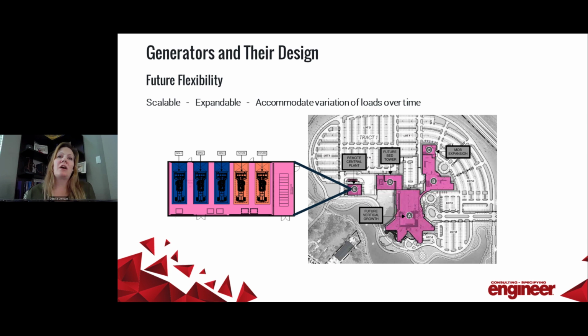All right, so let's now talk about how we make our generator system future-proof by providing the most flexible and scalable design as possible that fits within our owner's budget. So it requires appropriate space planning, adequate capacity in the distribution systems. So while you're assessing the loads and determining that ultimate redundancy desired, it's really important to understand the ultimate planned growth for a facility. You know, perhaps there's planned expansion on the campus, or maybe they can't afford to put all of their desired loads today, such as large centrifugal chillers. Maybe they can't afford to put those on emergency power right now, but they want to in the future. So you've got to plan for that space and flexibility.